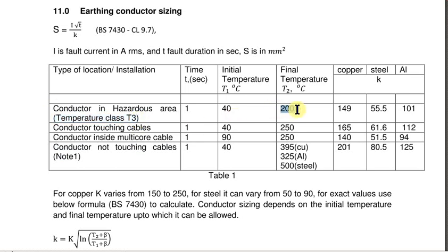If a conductor is touching other cables, the temperature has to be restricted to 250 degrees Celsius. The reason is an XLP cable outer sheath can withstand a temperature up to about 250 degrees Celsius before it can get deformed. Hence, we need to restrict the earthing conductor temperature to 250.